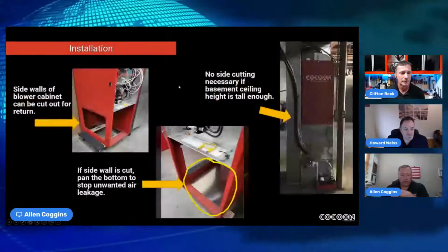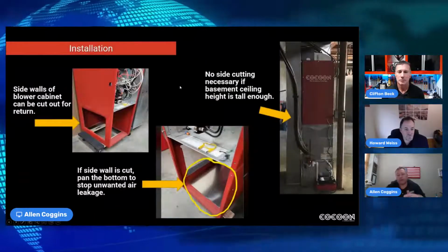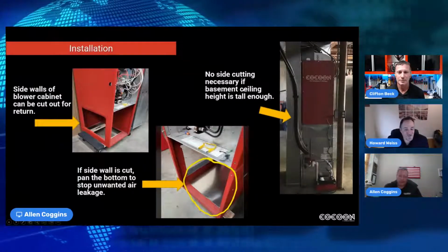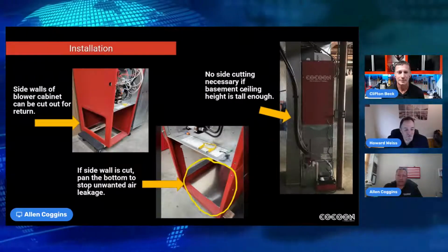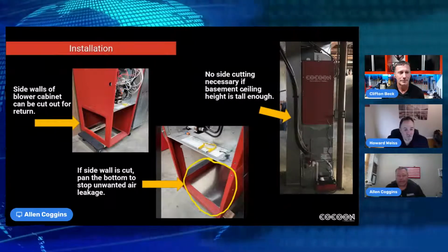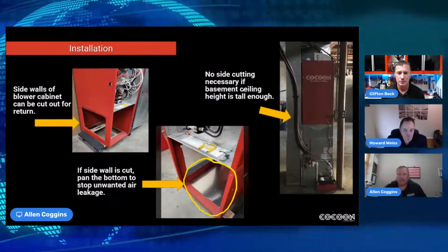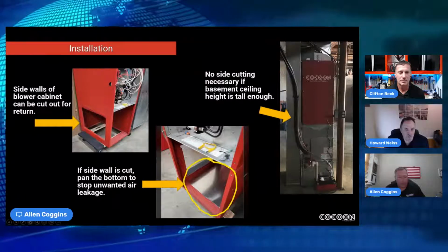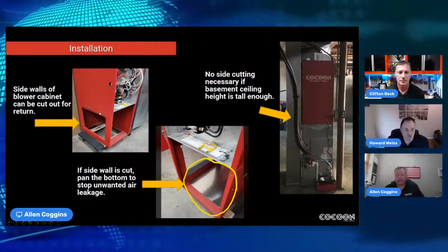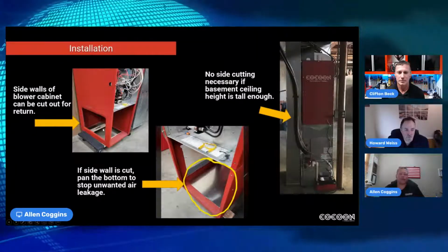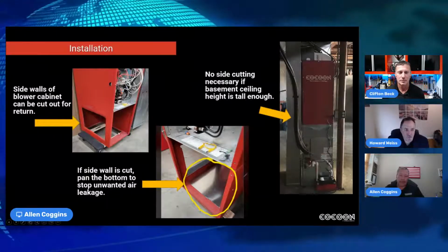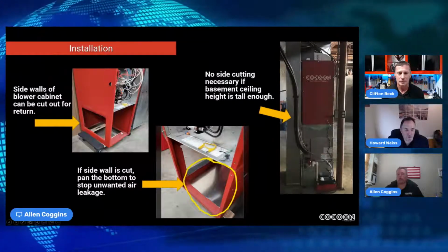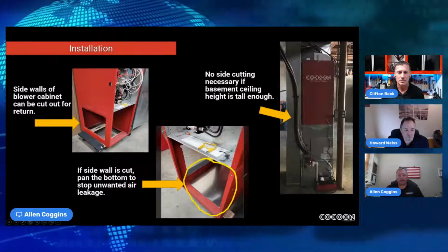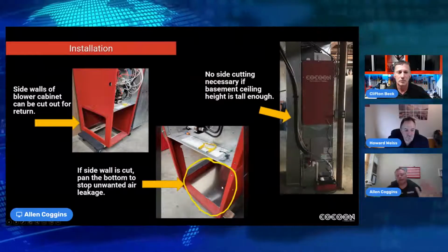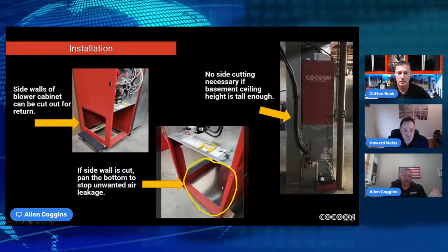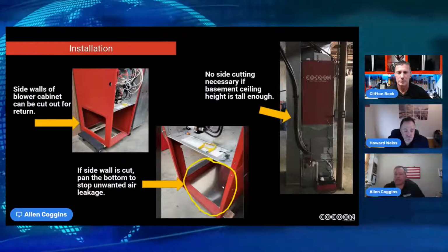The installation of our furnace is kind of a hybrid between a gas system and an electrical system. On a gas system you can cut the side of the blower out; most conventional electric furnaces you're not doing that with. We do not pan the bottom off, our bottom is open, so if you do cut the side out, pan up the bottom so you don't pull in basement air or attic air.